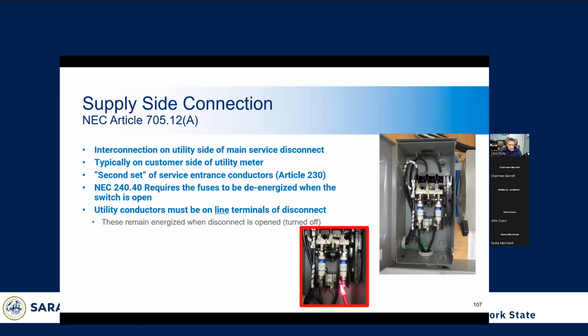Here we have a situation where you have a disconnect where the wires were not installed correctly. You can see down here a non-contact voltage tester is being used, and the system is open, but there's still voltage in where the fuses are. What happened is they installed the conductors that should be going in to the bottom at the top, and then vice versa. And so no matter what position this disconnect is in, the fuses are always energized, and so you can never really safely change the fuses. So that's an important thing to keep in mind when having disconnects installed.